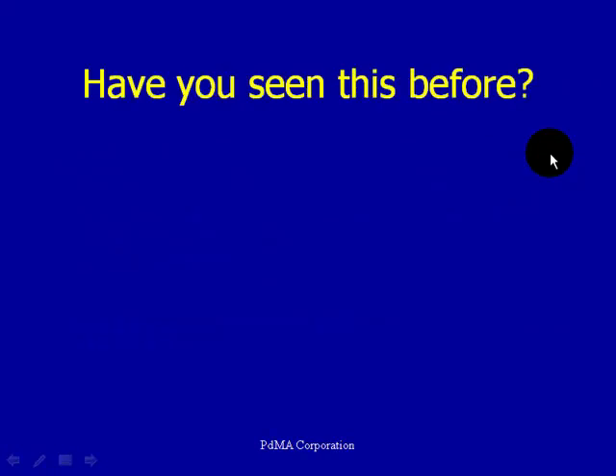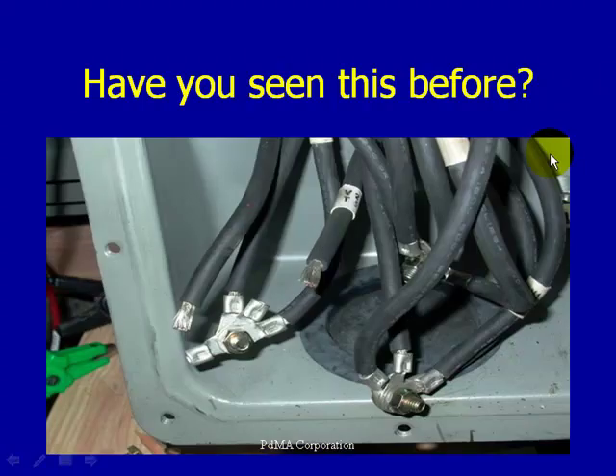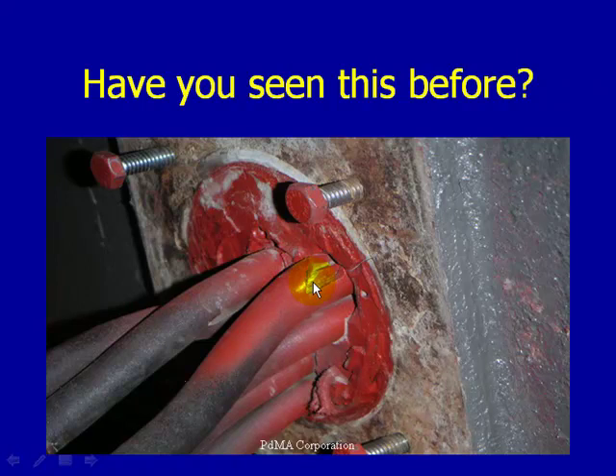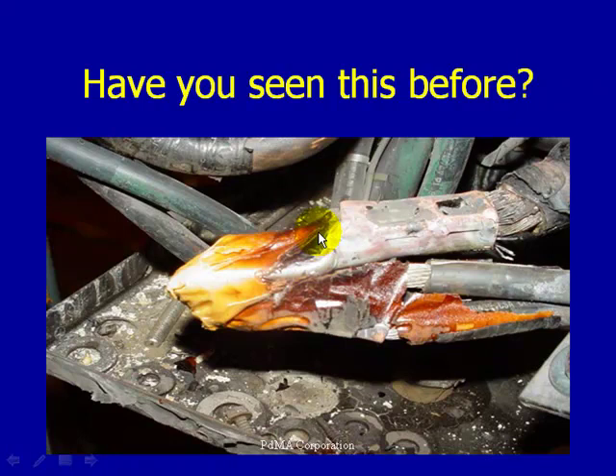Let's take a visual look at some potential power circuit issues. Here inside a motor connection box, we can see conductors that have essentially pulled out of the crimping — they appear to have been crimped, but not to spec. We also see where insulation was cut, possibly cutting some of the strands, creating resistive imbalance. Cutting those strands reduces the ability to carry current through those conductors. We can also see exposed copper and corrosion on exposed material, all of which reduce motor efficiency.